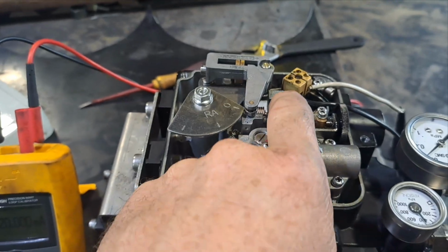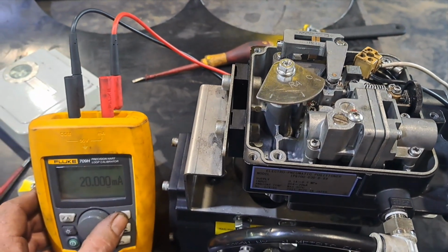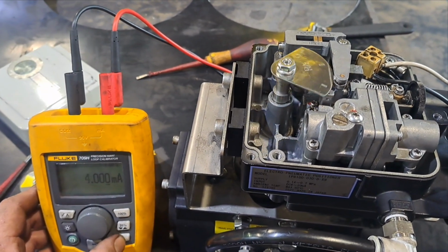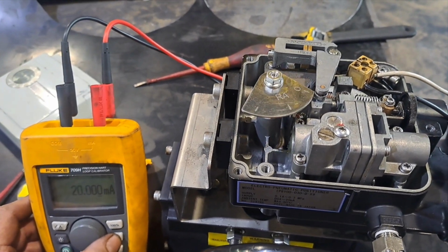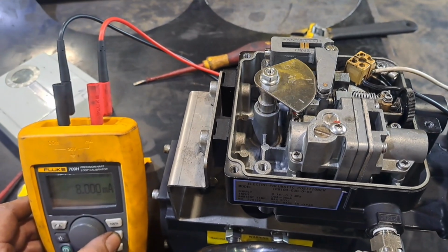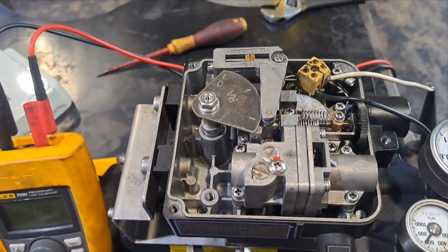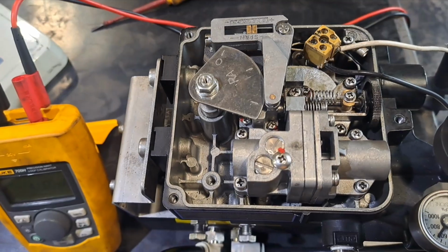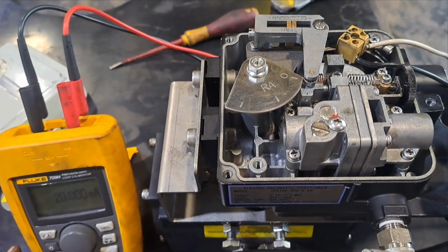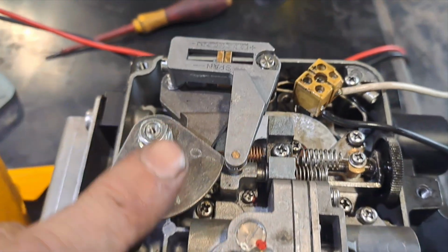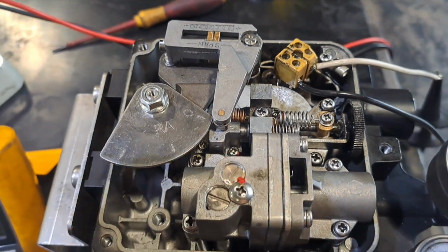With this setup, just like the previous one, the 4 milliamps opens the valve. Because of that, we got to make sure that the output on the PLC is swapped over, meaning that the 0% output on the operator screen will kick out 20 milliamps, and for 100% open, it'll kick out your 4 milliamps. Again, this is for fail-safe, to fail in the open position, because the fail will be a 0 milliamp if the cable gets cut or you lose power. That will mean the 4 milliamp is where your fail-safe would be. And this is for the open position.